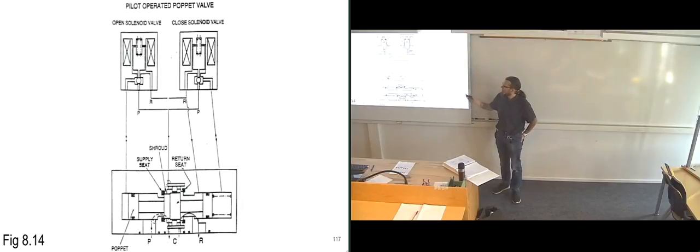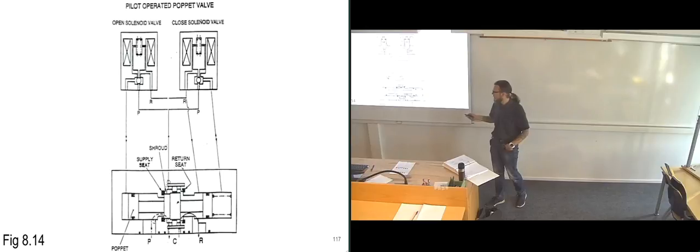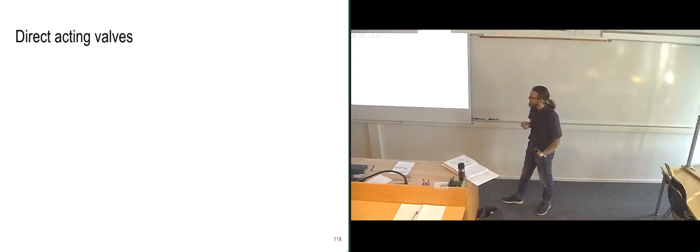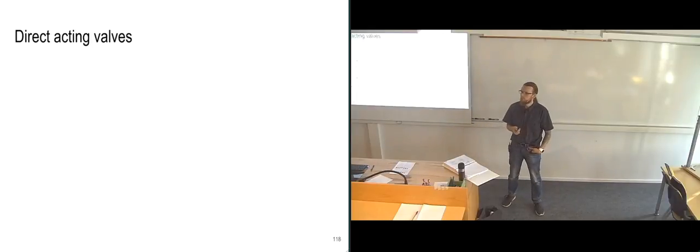So you can use quite a small amount of power to operate these valves because they are very small, but they are strong enough to move the slide inside the main hydraulic valve. And when this slide has been moved, then you get the hydraulic pressure flow into wherever you need it to go. Yeah, we'll do a break.